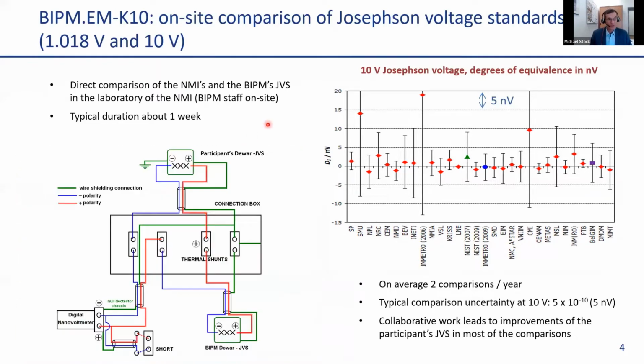And what they're actually doing is shown here. So they both have a Josephson voltage standard. They are connected in opposition. So here by the red line, the 2 high potential sites are connected directly. And between the low potential sites, we're measuring the difference voltage with a nanovoltmeter. This then allows to determine the differences between the realization of the 2 Josephson voltage standards for the same nominal voltage of either 1 volt or 10 volt.